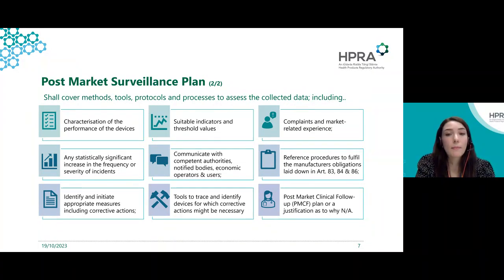It should include methods to manage trend reports, including protocols to be used to establish any statistically significant increase in the frequency or severity of incidents. It must cover the means for communicating with competent authorities, notified bodies, economic operators and users, and it must reference the procedures in place to comply with post-market surveillance obligations.